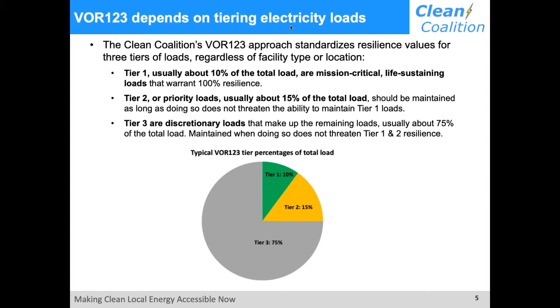Tier one is usually about 10% of the load, and these are mission critical, life-sustaining loads that really warrant 100% resilience. Tier two, or priority loads, are usually about 15% of the load, and these should be maintained as long as doing so does not threaten the ability to maintain tier one loads. Tier three are the rest of the loads, discretionary loads that are usually about 75% of the total. Tier three loads are maintained only when doing so does not threaten tier one and two resilience.